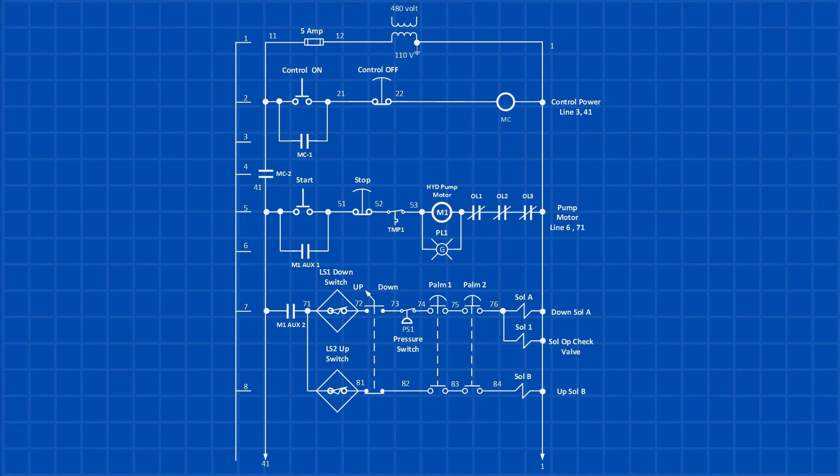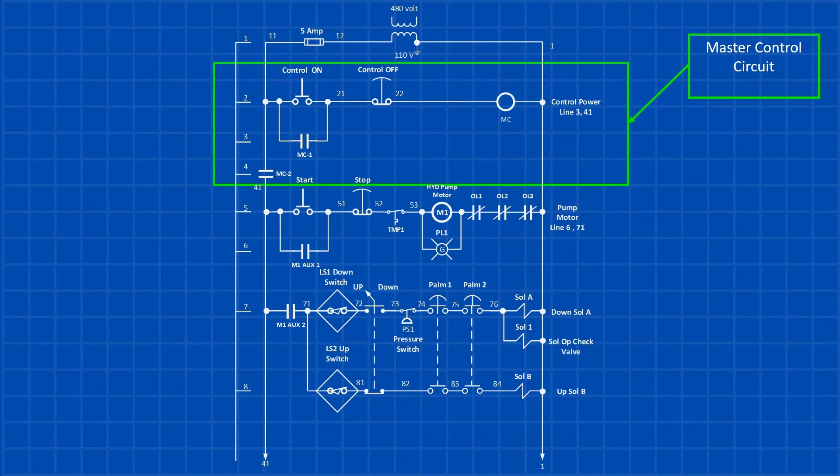Now let's look at the press ladder diagram. The first section of this ladder diagram is the master control circuit, which you'll typically find in most control panels. The master control relay, MC, is a latching relay that powers the entire circuit once energized.